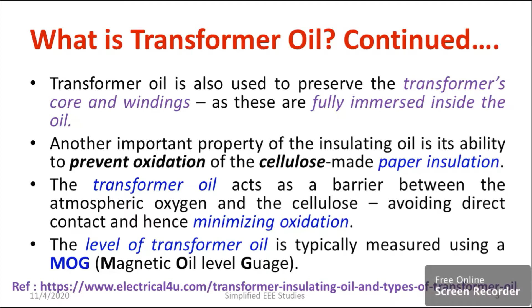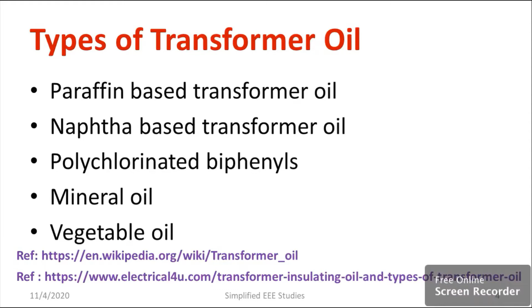So these are the fundamentals of transformer oil. Now let me ask: how do you classify transformer oil? What are the different types available? There is paraffin based transformer oil, naphtha based transformer oil, similarly polychlorinated biphenyls, mineral oil, and vegetable oils - these are the various types. Paraffin based transformer oils are most popular because they are plentifully available, and moreover, they can withstand high temperature. That is why paraffin based transformer oils are most popular. Similarly, you can use mineral oil, vegetable oils, etc. Even coconut oil can be used - research is still proving that we can use coconut oil, and R&D is still going on.